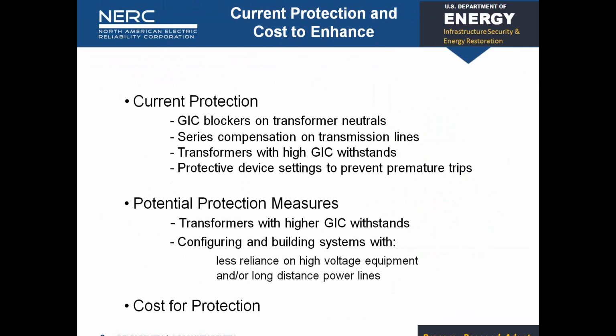Like I said, it's typical in western utilities. A lot of it's going into Texas right now because they're putting a lot of new power lines in to connect to all of the new wind that they're putting in. And they're putting series compensation on those lines, not to block space weather, for efficiency of the lines and other reasons. But it's giving you that protection. So as you do assessments to say where I might need to put a blocker, if it's already blocked from these various lines, those are just things that have to be taken into consideration.